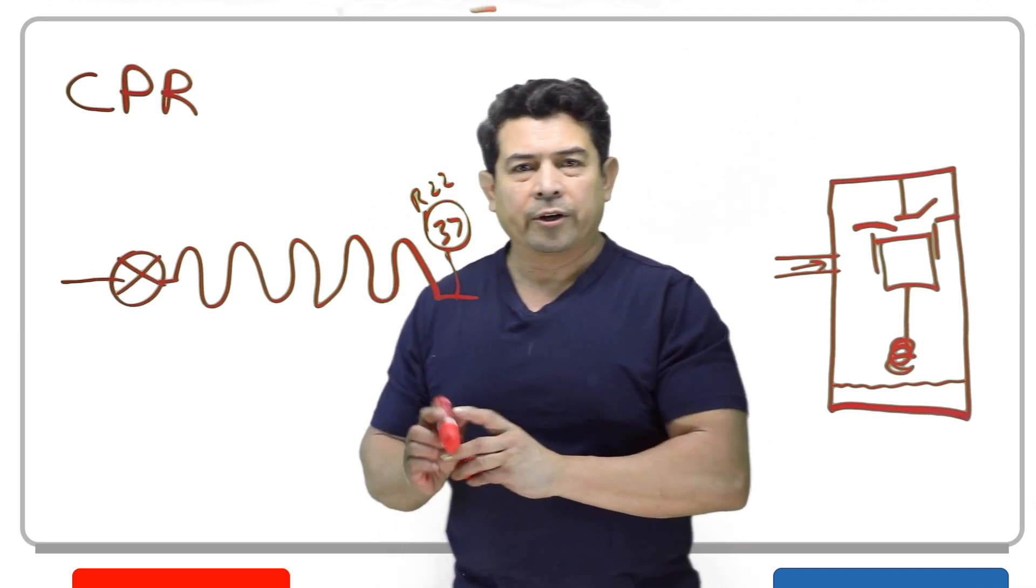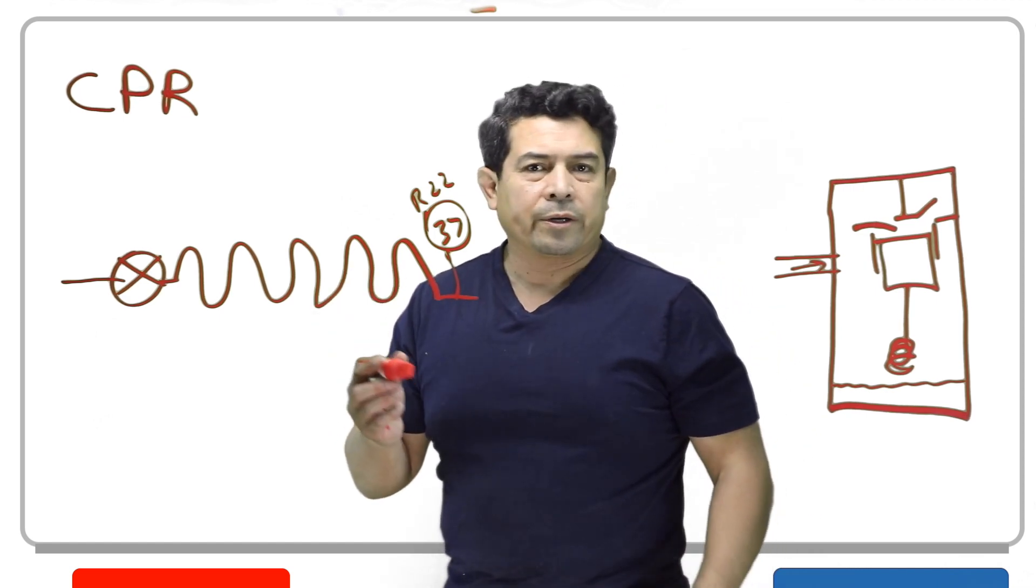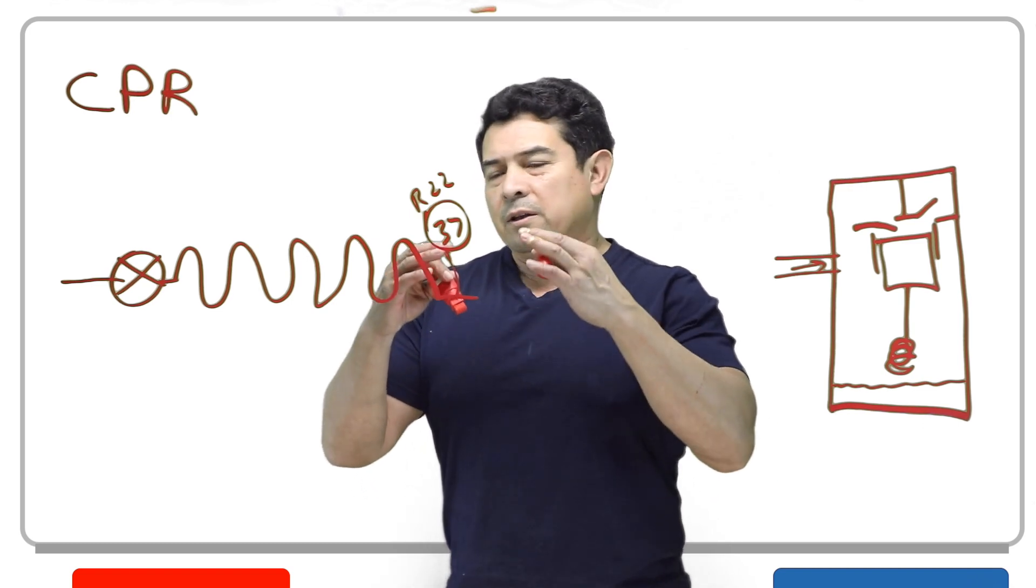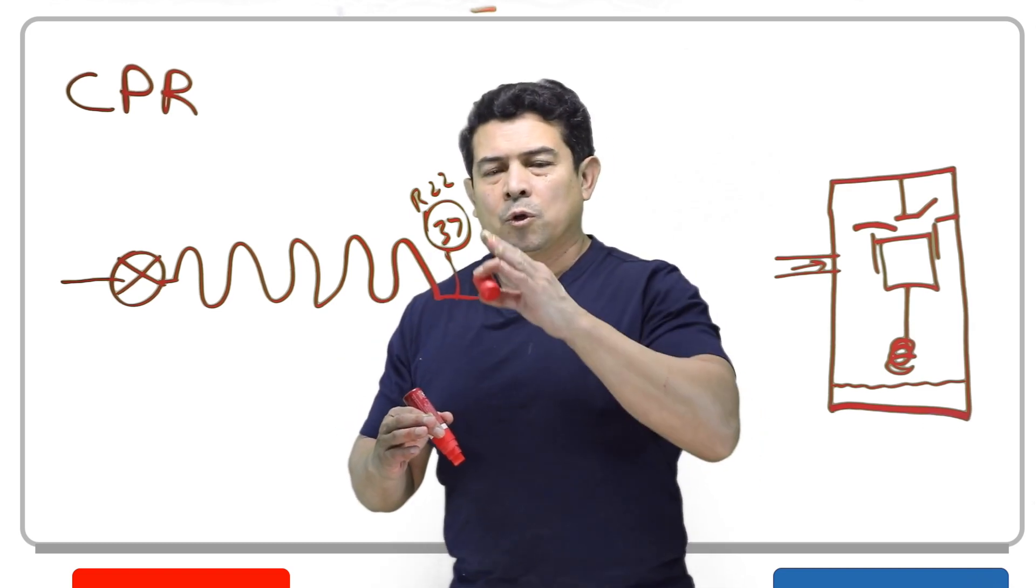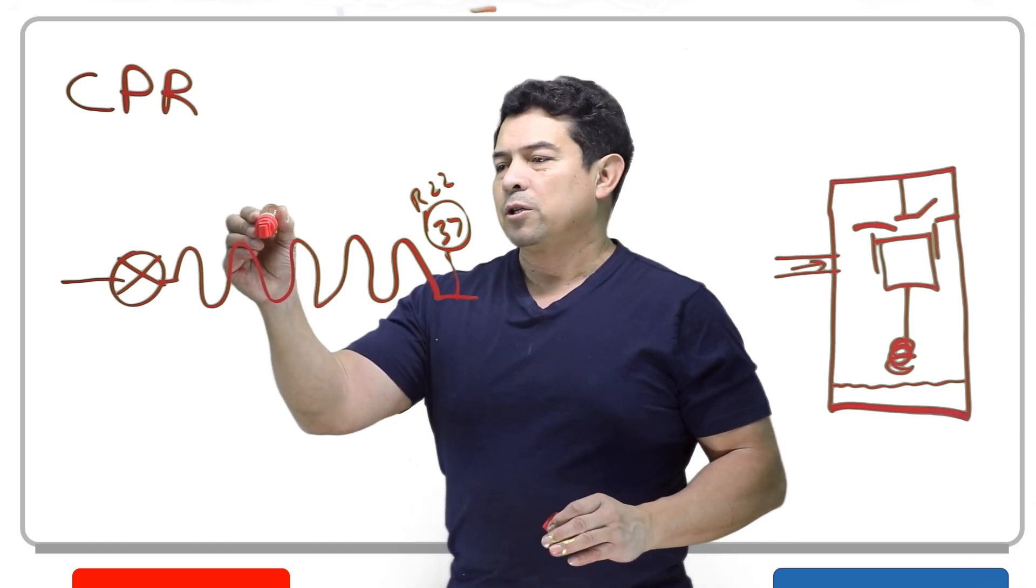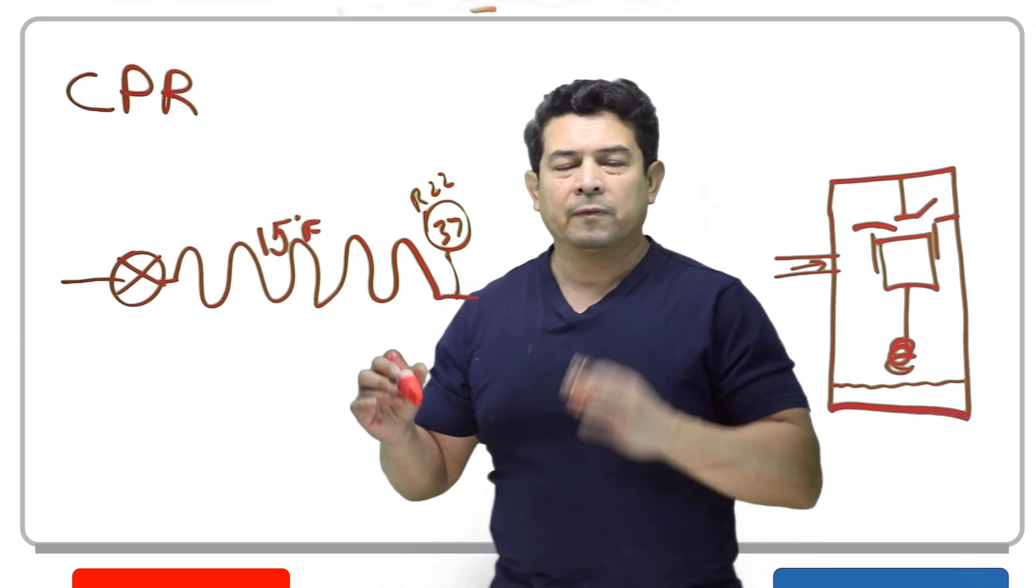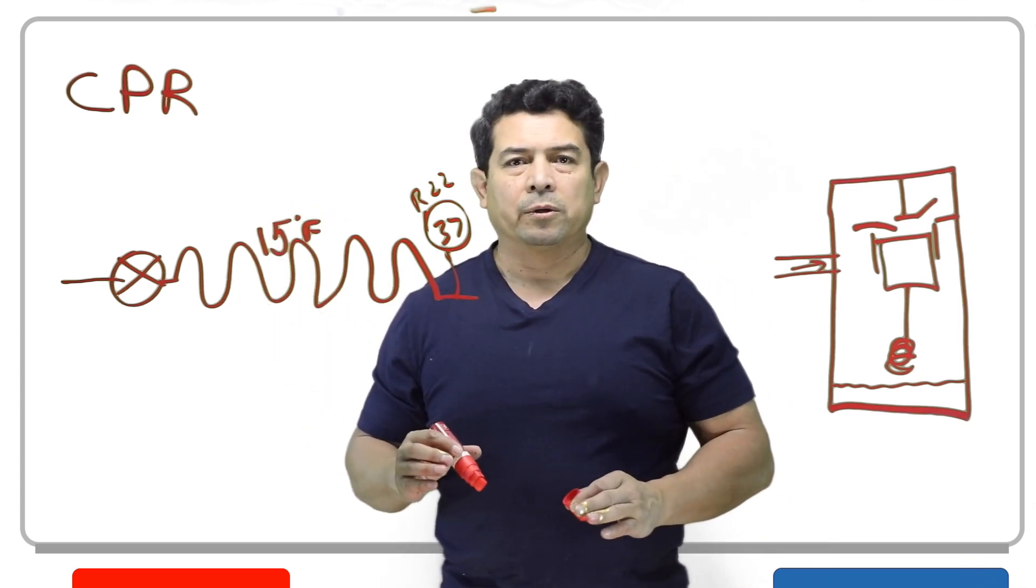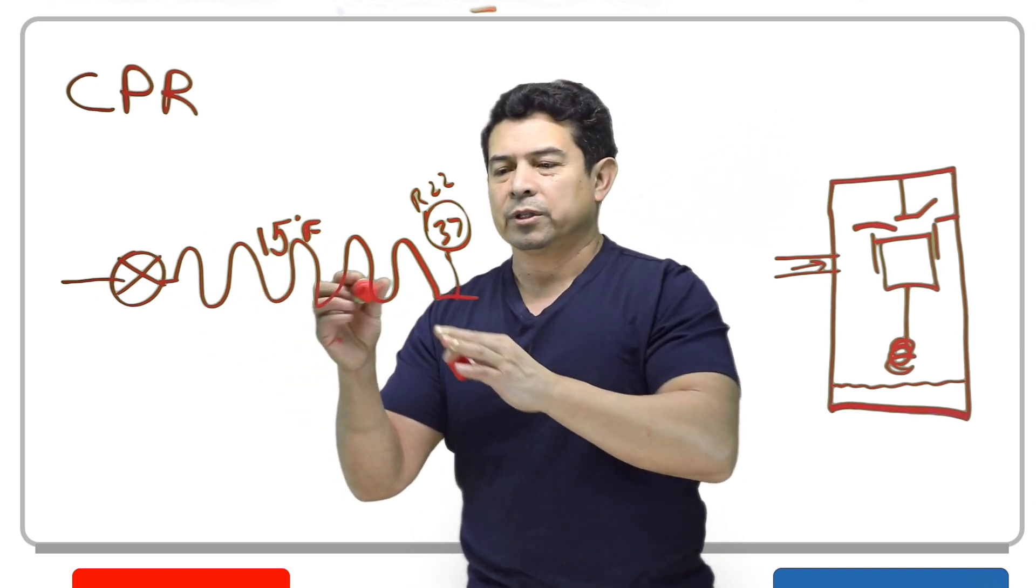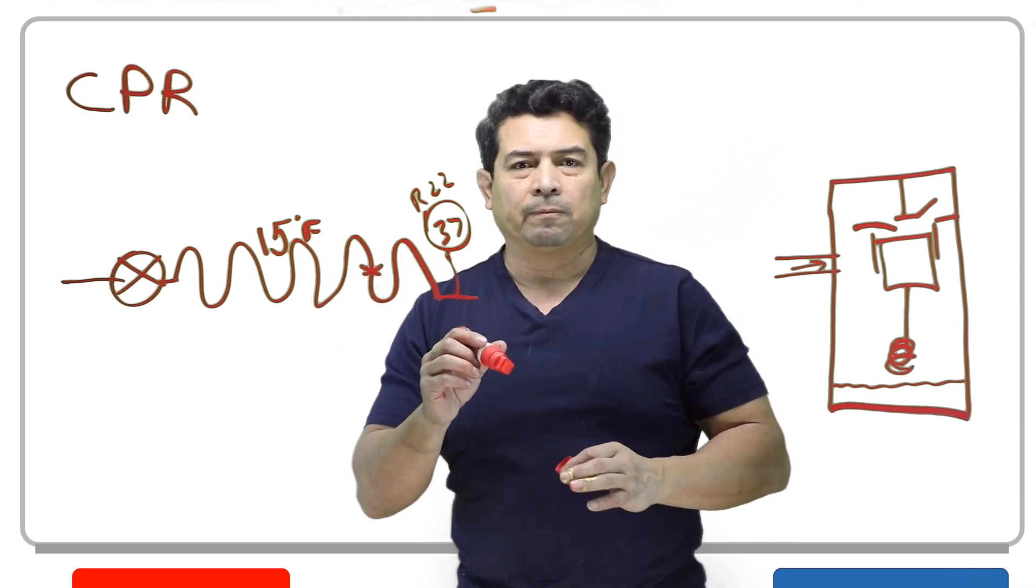Let's say that this is not on an air conditioning system. Let's say this is on a refrigerator or a freezer or something that keeps the food very cold. When we look at a PT chart, 37 is going to convert to approximately 15 degrees Fahrenheit. So that's the temperature of this coil. This coil, because an evaporator is still going to evaporate the refrigerant and at some predetermined point is going to start to superheat it.